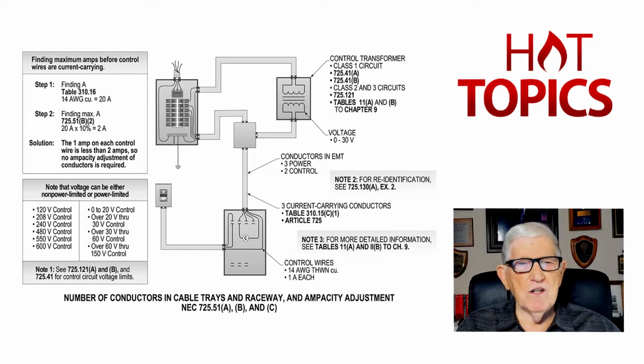And notice in the illustration, left-hand side of the illustration down at the bottom, you see the non-power limited circuits: 120, 208, 240, 480, 550, 600 volts, see? And then to the right, you see the power limited circuits, where you have to go to your Table 11A and 11B, as well as C, there in Chapter 9 of the NEC. That's Note 3 that we're looking at on the right-hand side of the illustration down at the bottom. And then Note 2 is just re-identification, where you can re-identify these circuits under certain conditions.